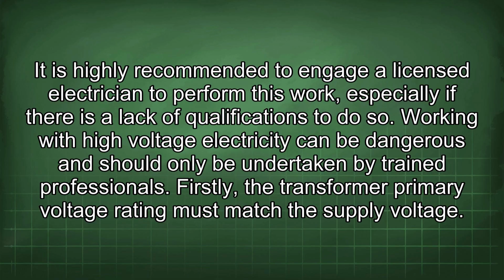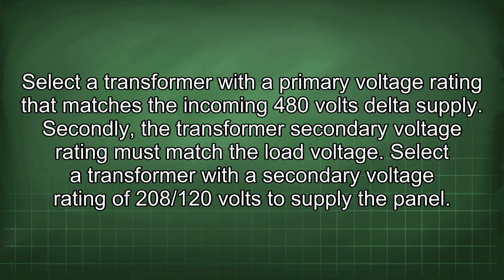Firstly, the transformer primary voltage rating must match the supply voltage. Select a transformer with a primary voltage rating that matches the incoming 480 volts delta supply. Secondly, the transformer secondary voltage rating must match the load voltage. Select a transformer with a secondary voltage rating of 208/120 volts to supply the panel.